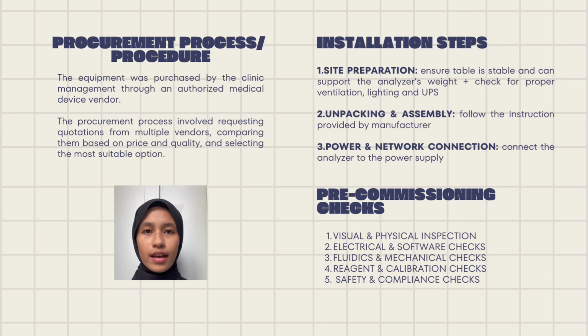First, site preparation. Ensure the table is stable, can support the analyzer weight, and check for proper ventilation, lighting, and UPS. Second, unpacking and assembly. Follow the instructions provided by the manufacturer. Third, power and network connection. Connect the analyzer to the power supply.